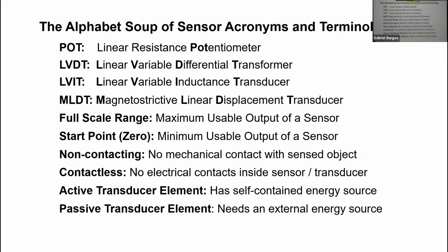Now the non-contacting, this comes up because you'll see in a chart later that it has non-contacting and other times it says contactless, okay? Non-contacting means you don't need any mechanical contact between the sensor and the position device you're trying to measure. Contactless means there's no electrical contacts inside.